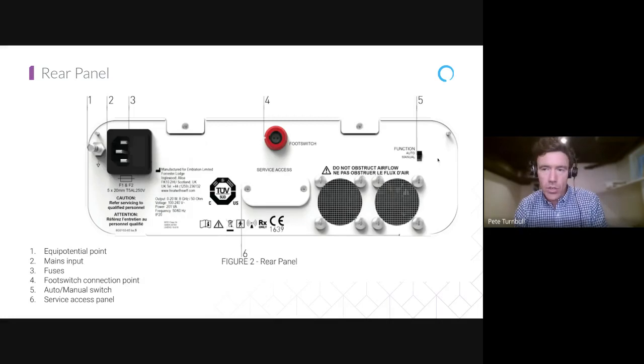The one thing I do want to draw your attention to is this auto or manual switch. You're going to want to make sure this is in auto mode when you're doing your treatment. What that means is when you press the button, the system will deliver the time that is set on the system. You just press it once, and then it counts down from 2, 1, 0 and gives you exactly that amount of power. If you have it on manual, if you press the button once, it'll only deliver a little burst for as long as you press the button. In manual mode, you have to hold it down, and then you're trying to calculate yourself how much time is passing, and it's a much less accurate treatment.